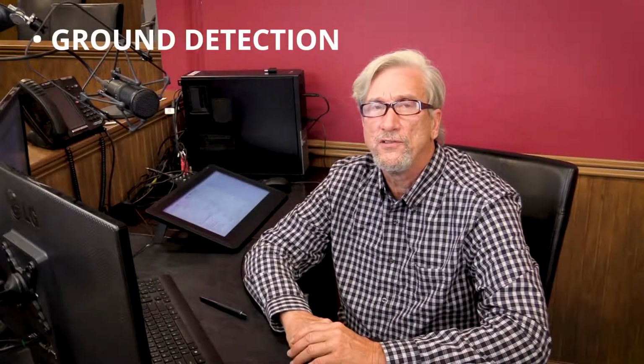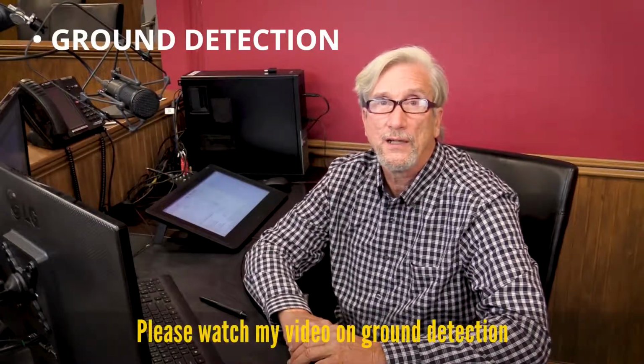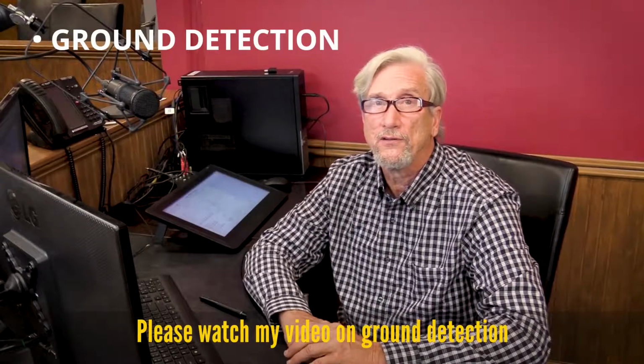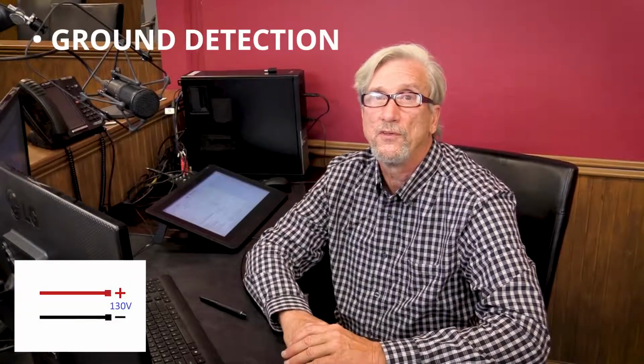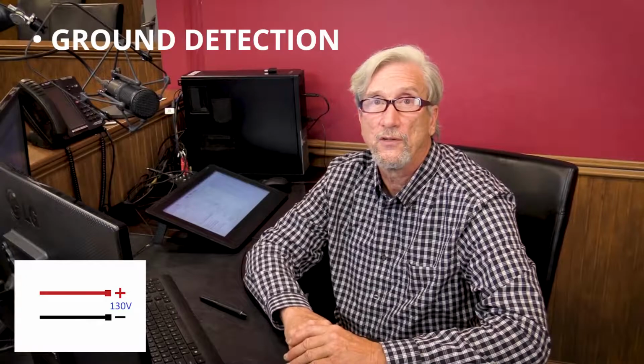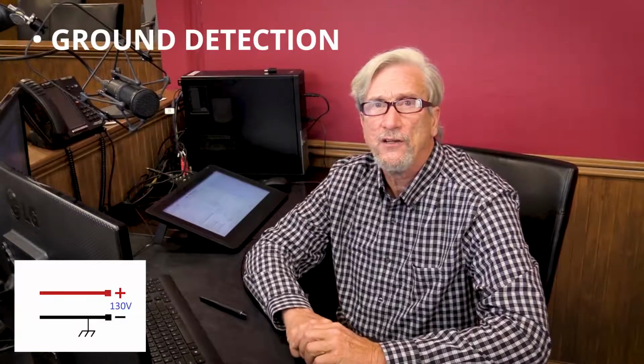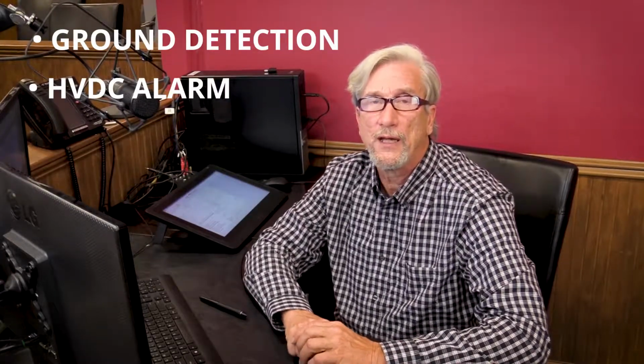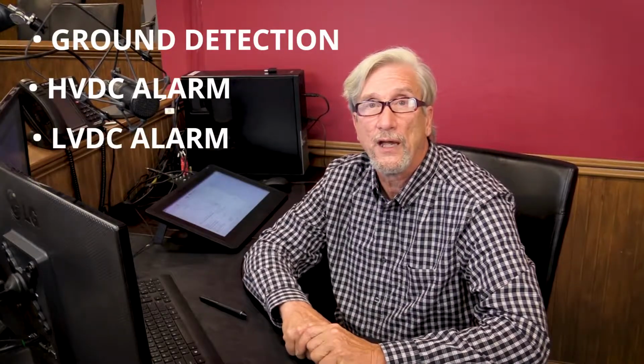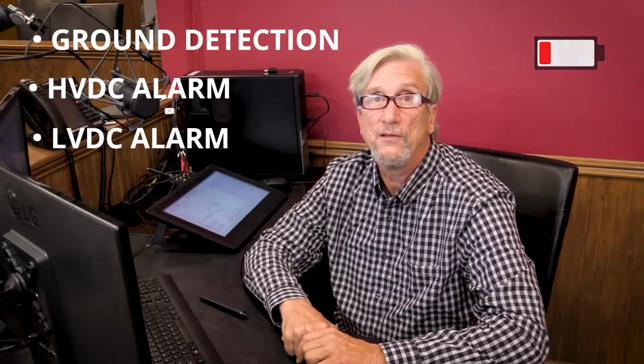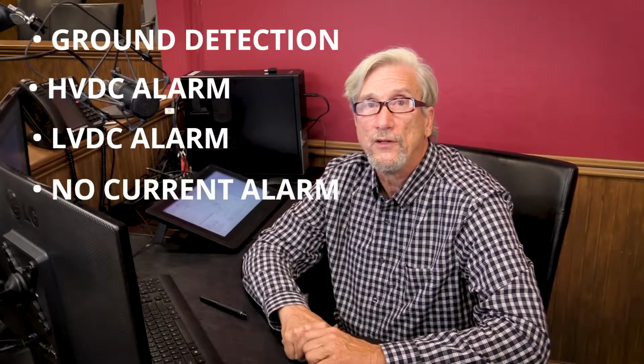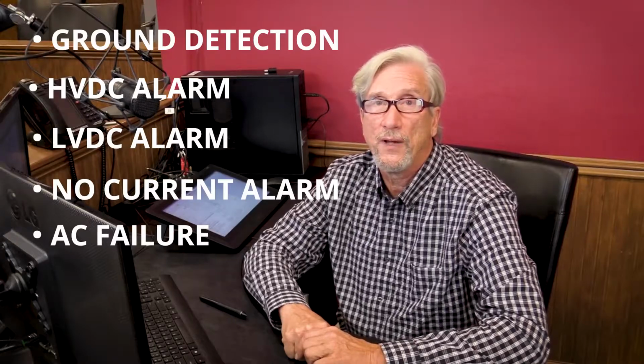My motto is, if you have lots of options, you're going to have lots of options. In a battery charger, that's what we put in there for the customer: to monitor the output voltage, the input voltage, the output current, and we also monitor ground detection. These are important for a DC system because the DC bus is usually floating, not connected to ground, as opposed to AC. Because of that, in 130-volt or 260-volt battery charger systems, there's a positive and negative ground fault alert to let the customer know he has that connection made. Other things they look for are a high-voltage DC alarm that might hurt the battery, and a low-voltage DC alarm that tells you the battery is deficient in power to support the loads when needed. There's also a no current alarm and an AC failure alarm - these are common in almost every battery charger.